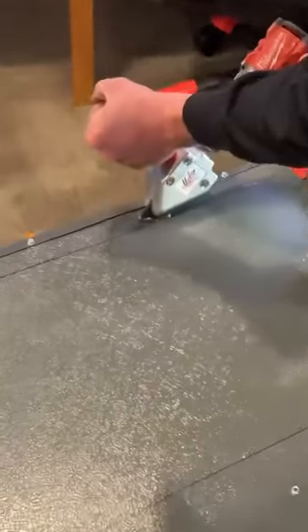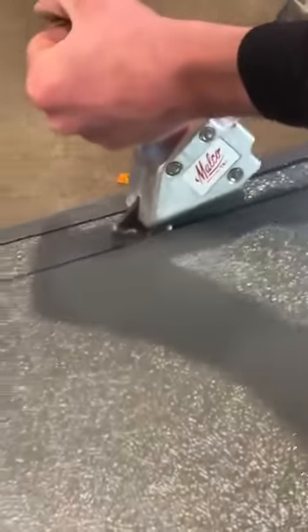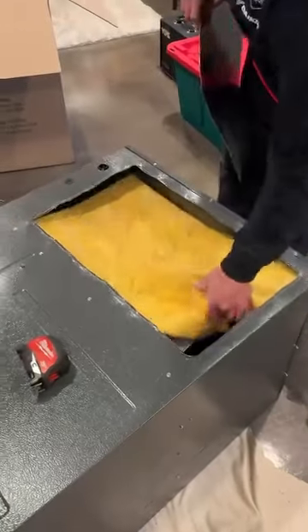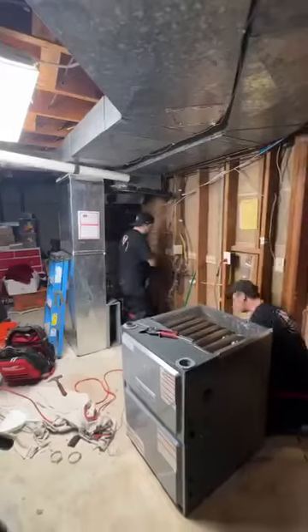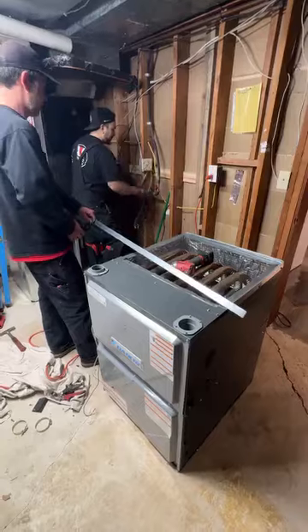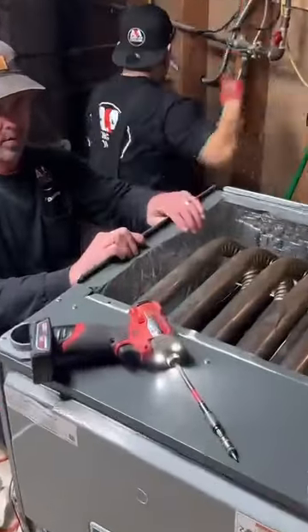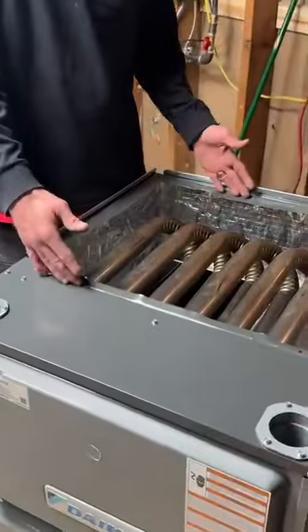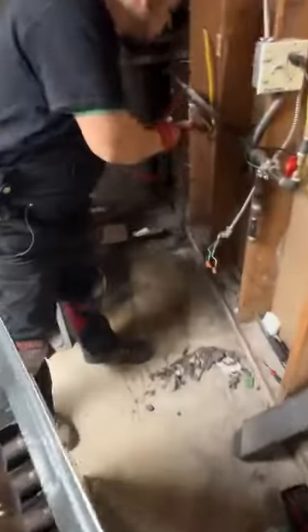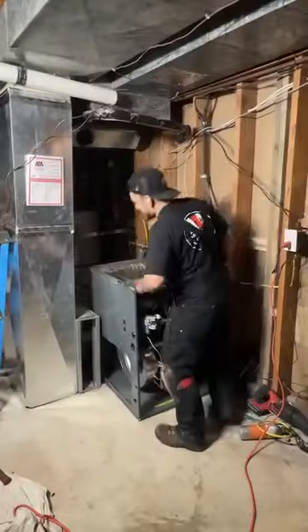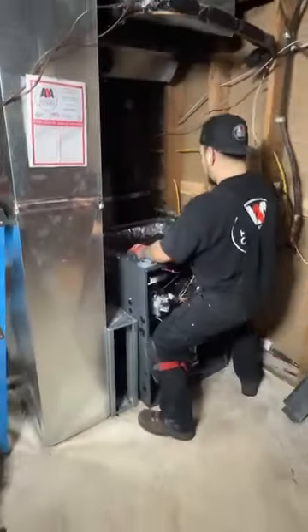Next, we begin cutting the accessibility for the return ductwork and filter cabinet to attach to the new system. Next, we add the outside framing to the new unit that the coil will sit on top of and within in order to hold it in place. After that, we clean out the existing space for the new furnace and coil to be put in and put the new furnace into its position.